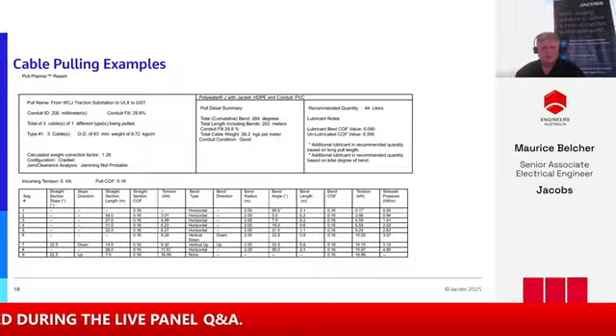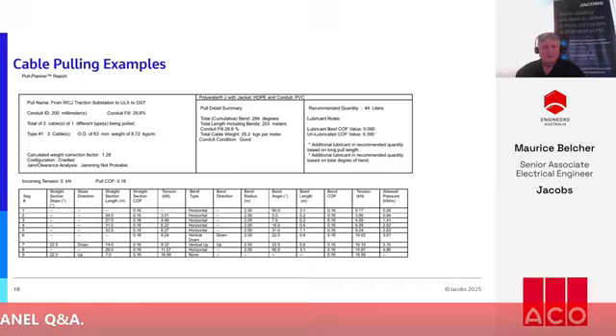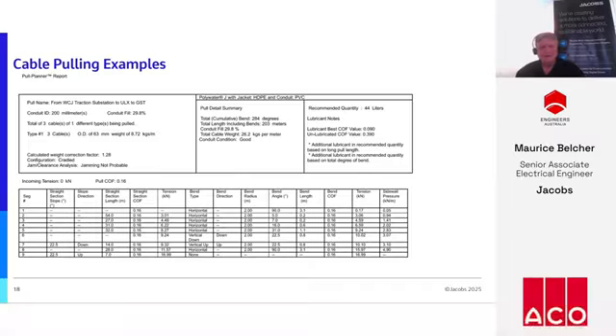Here's an example where the software models the pulling and can tell you the tension required, and interestingly, the quantity of lubricant required. You can see in the table that it accounts for all the horizontal bends and key vertical bends as well, because in any electrical infrastructure that's the key part - coming out of an electrical device, going down into the ground, and then coming back up into a device.